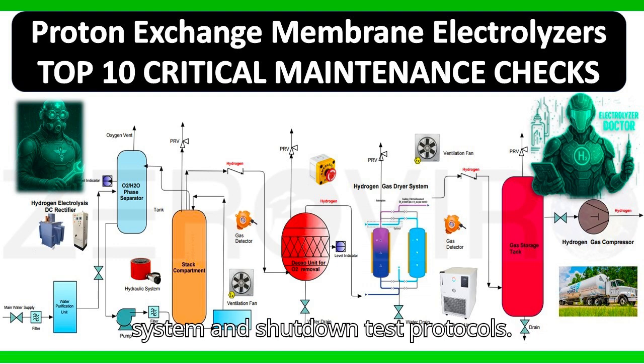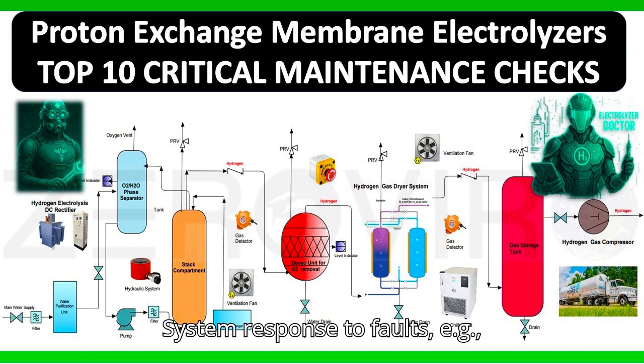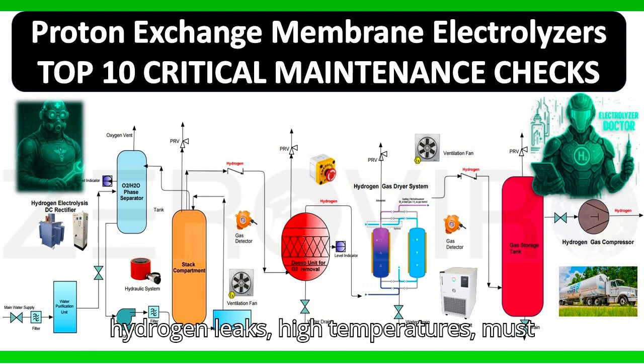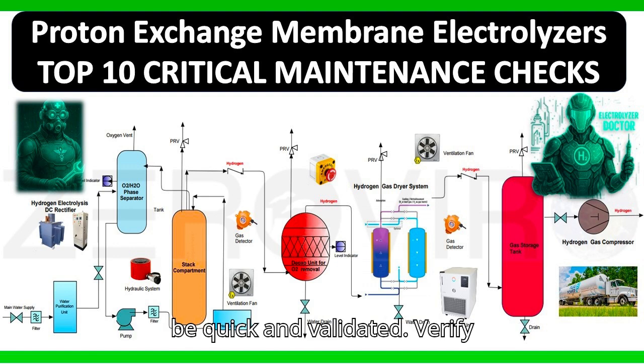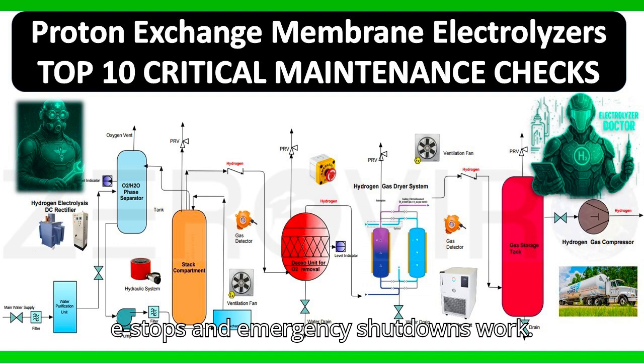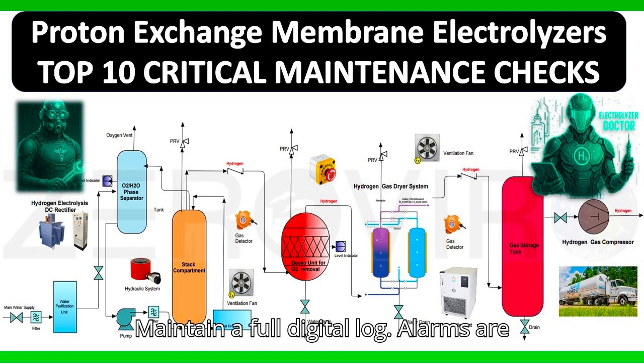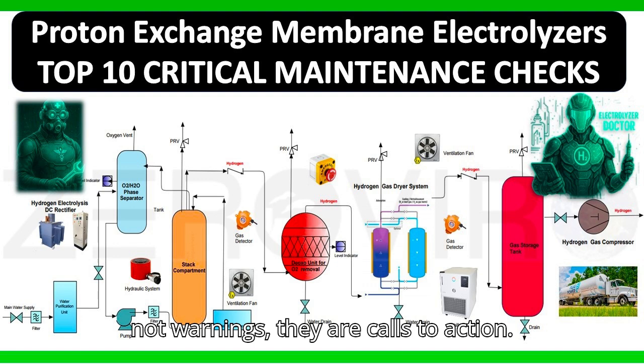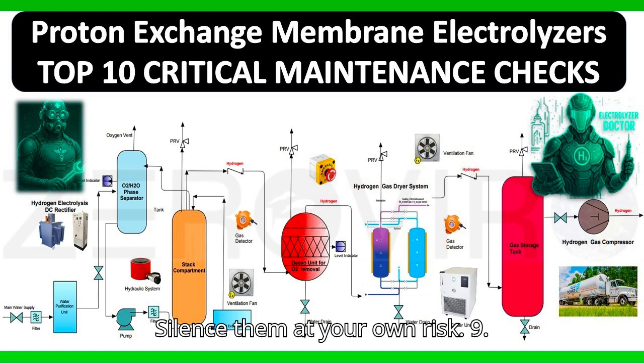8. Alarm system and shutdown test protocols. System response to faults, e.g., hydrogen leaks, high temperatures, must be quick and validated. Verify e-stops and emergency shutdowns work. Maintain a full digital log. Alarms are not warnings, they are calls to action. Silence them at your own risk.